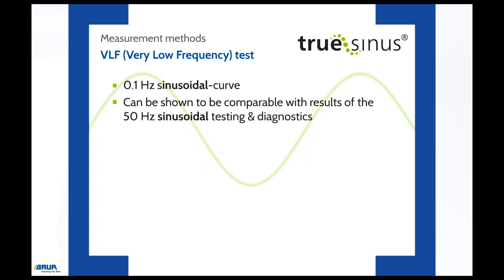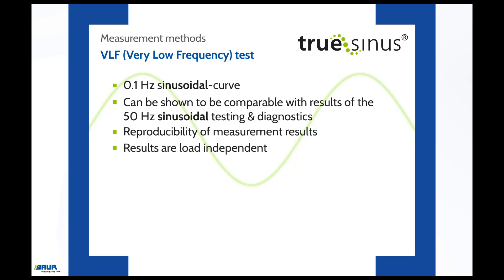Baur's VLF, or Very Low Frequency Test, is based upon a sine curve with a frequency of 0.1 Hz and can be shown to be comparable with the results of 50 Hz sinusoidal testing and diagnostics. This comparability has been comprehensively tested in practical everyday situations by field measurements and has proven its value in numerous studies. The most important factor in VLF testing is the reproducibility of the measurement results — the influence of the measurement system upon the result is minimized, making results load independent, a clear advantage compared to other methods.